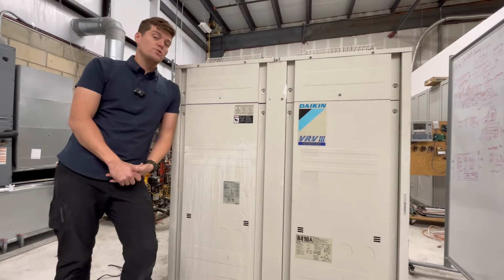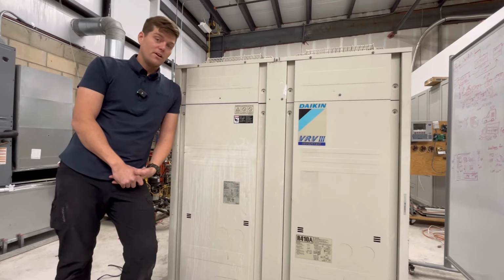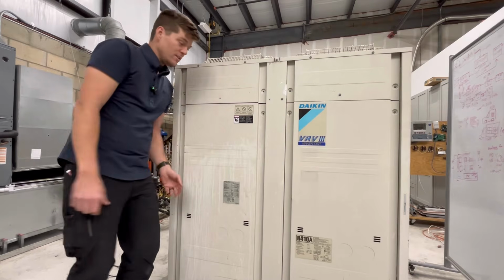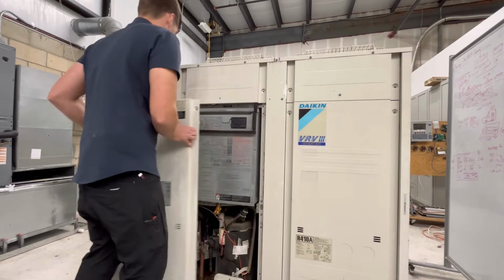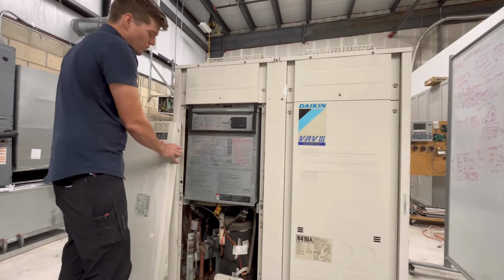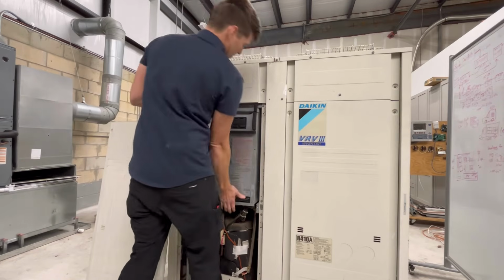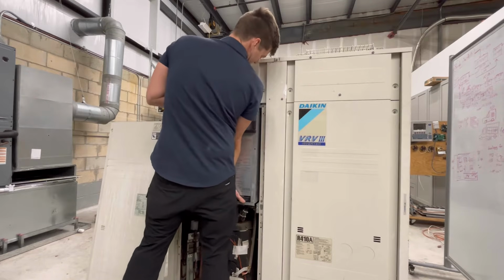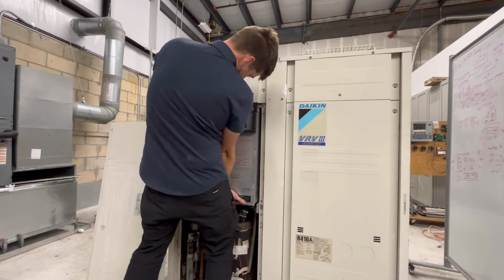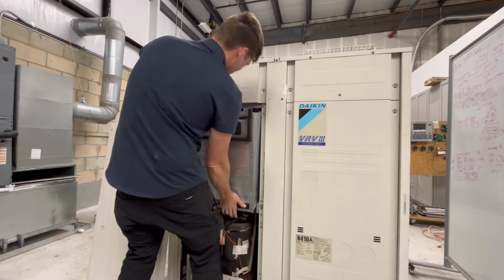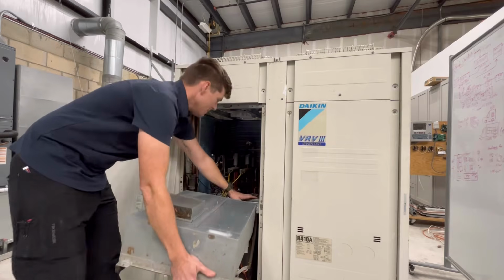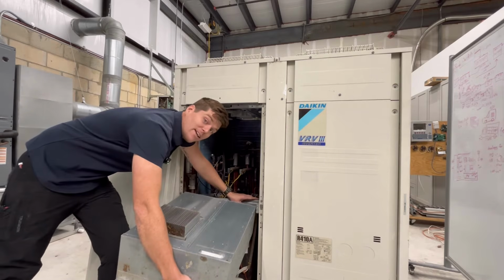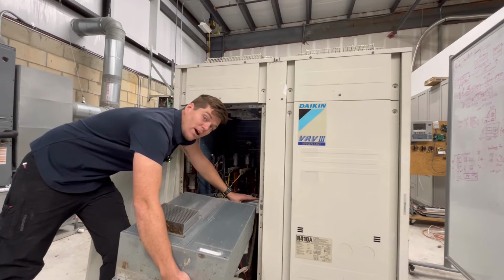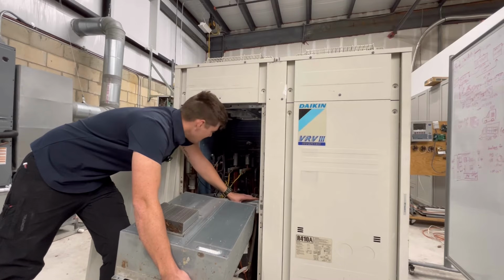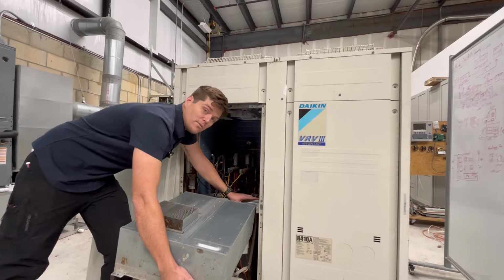Four-way valves are one of those tricky things to diagnose on VRV and VRF equipment because, let's be honest, the serviceability on them is, we'll use the word, subpar. But as you can see, even after I get in the cabinet itself, get access to the valve itself, they're all the way in the back. So sometimes troubleshooting four-way valves is not exactly the easiest thing to get to. But let's look at how to do that out in the field.